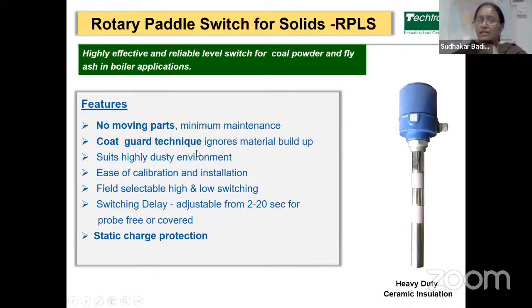Its coat guard technique ignores the material buildup. It suits highly dusty environments. Ease of calibration and installation, and field selectable high and low level switching. The switching delay is provided, that is adjustable from 2 to 20 seconds for probe free to probe covered. The static charge protection is provided for fly ash applications. So this is a heavy duty construction with ceramic insulation, generally used for high fly ash applications.